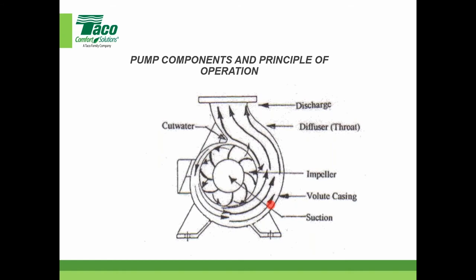We offer two different pressure ratings for most of our pumps, 125 and a 250, okay? I'm using US terms, US measurements. So some of you may have to bear with me on that, but nonetheless, it is important to realize that. And to be quite honest, well over 80, probably closer to 90% of our product line that we send out of Cranston is 125. The 250s may be for a higher high rise or something like that, or some different type of application. So just keep that in mind. Diffuser, throat, that's just a term that is it important for you folks? No, but at least you know what it is. Discharge makes sense, right? There, that's where the water comes out.